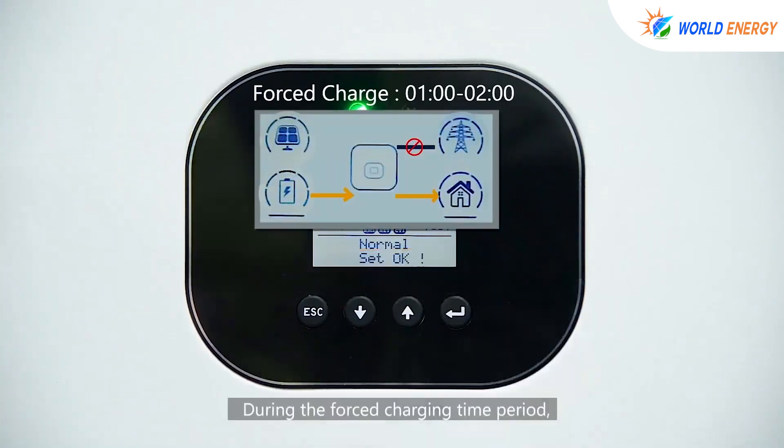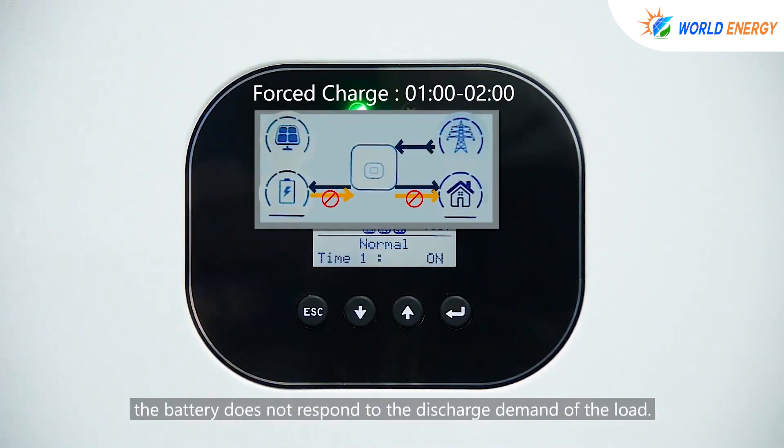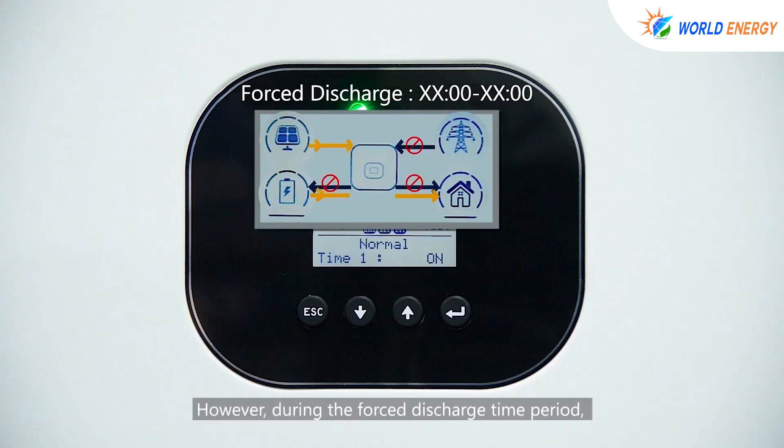During the force charging time period, the battery does not respond to the discharge demand of the load. However, during the force discharge time period, if the PV power is greater than the rated inverter power, the excess energy from the PV automatically charges the battery.